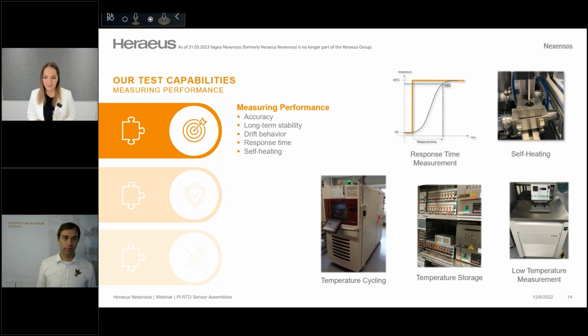And then we have the temperature storage test. This test is also specified in the DIN norm. A very standard test setup would be to expose the sensor to its maximum operating temperature for 1,000 hours. And sometimes maybe not the high temperature region might be decisive, but the low temperature region. That's why we also have in our validation analysis center a low temperature measurement, for example, to measure the cryo temperature range down to -196 degrees Celsius.